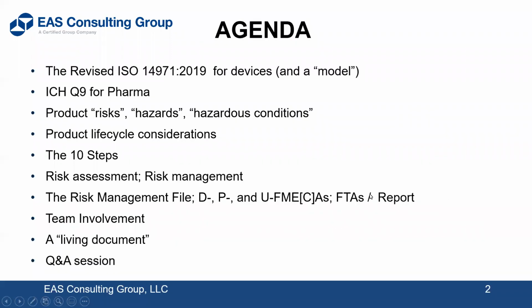So first of all, we're going to look at the latest revision of 14971, which is 2019. There were several other revisions, but the two most prominent we'll cite a couple of times is 2007, which said reduce risk as low as practical, and then 2012, which said reduce risk as low as possible, which created a lot of heartburn. And 2019 has changed back to allowing any number of different ways to reduce risk, but basically performing a benefit risk. They changed it from risk benefit to benefit risk analysis to show that the benefits outweigh the risk to the patient.